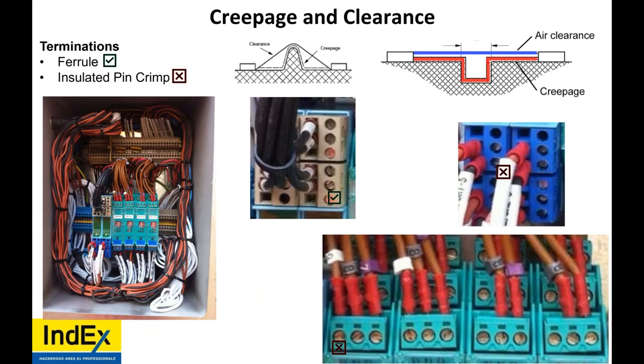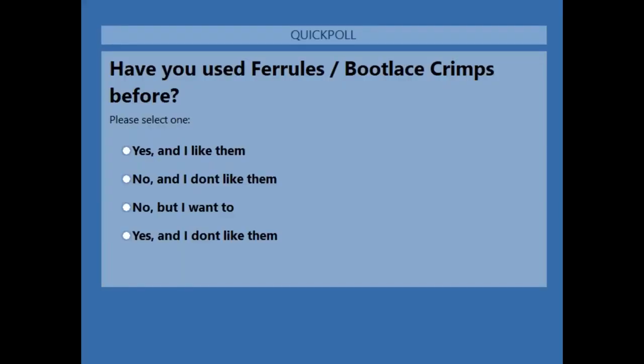Let's look at a real world installation. Right here, we have ferrules, nicely inserted, creepage and clearance distance is maintained. Now on these other ones where the insulated pin crimps are used, well, I can see metal exposed because the insulated pin crimp cannot insert into the terminal. Here's your issue. One of the issues with insulated pin crimps is they do not sufficiently insert into a terminal. Now, let's just ask a question. Have you used ferrules, bootlace crimps, core end sleeves, all the same meaning? Yes or no? And you like them? Do you not like them? If no, would you like to use them?